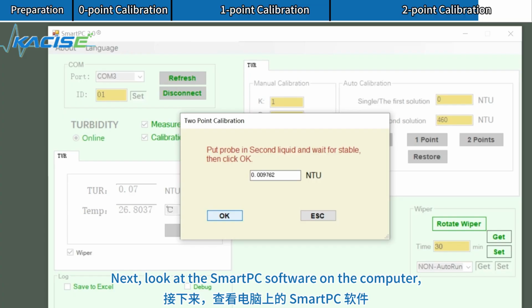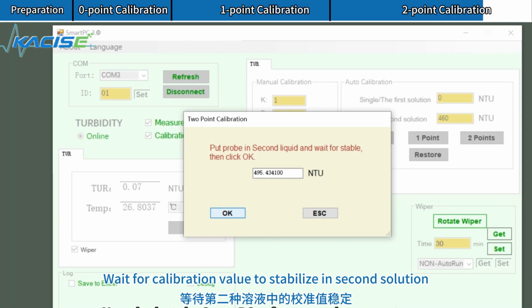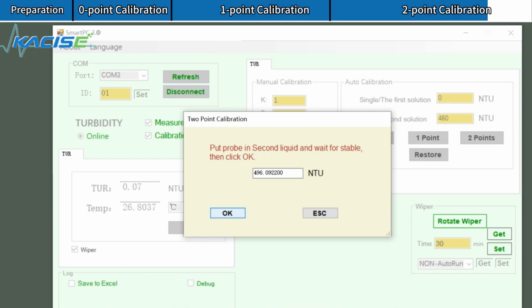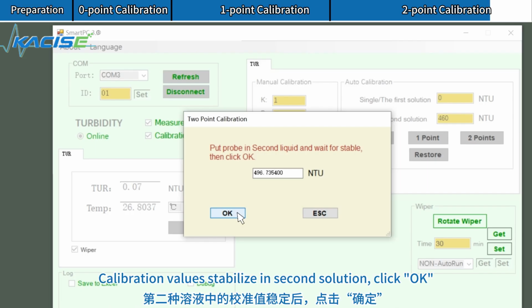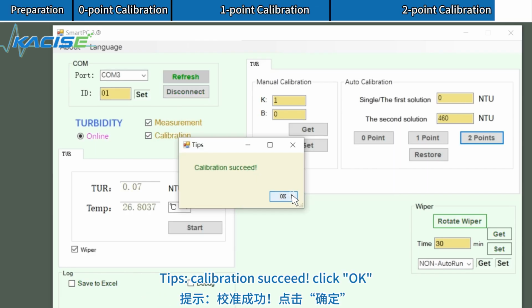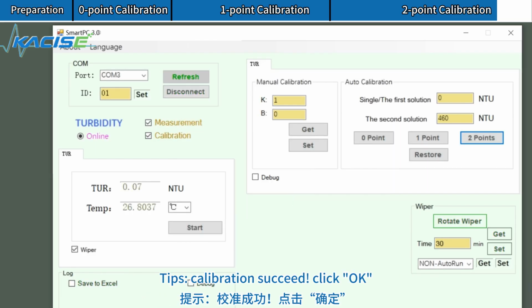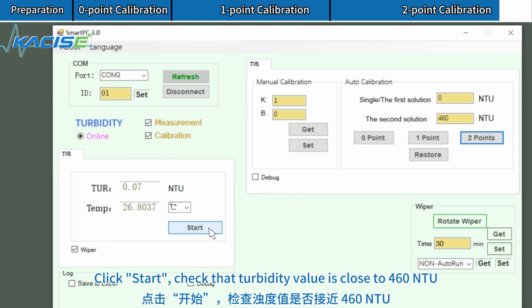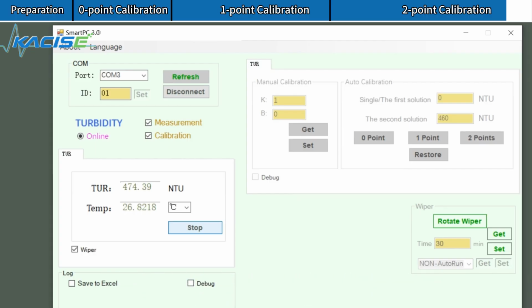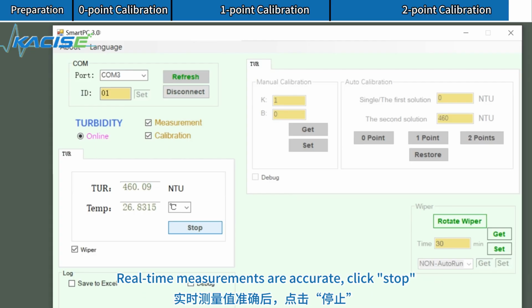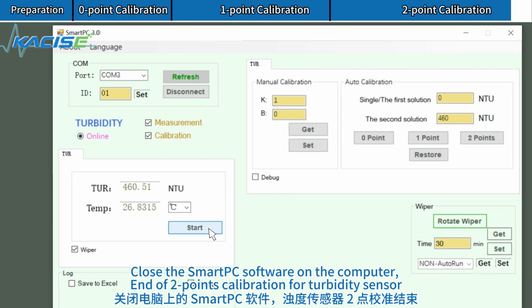Next, look at the Smart PC software on the computer. Wait for calibration value to stabilize in second solution. Calibration values stabilize in second solution. Click OK. Tips: calibration succeed. Click OK. Click Start. Check that turbidity value is close to 460 NTU. Real-time measurements are accurate. Click Stop.